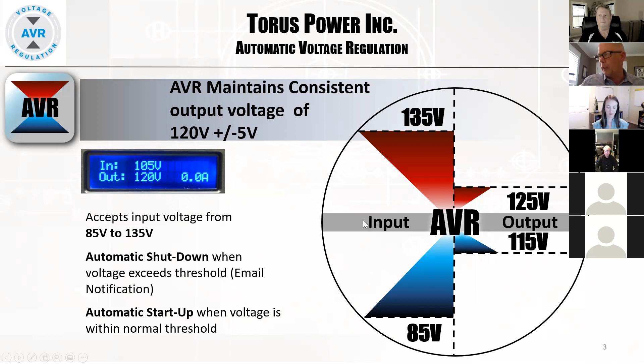So what we do on the automatic voltage regulation units is we have different starting points or different input taps on the primary winding. So we can change the size of the primary winding in relation to the secondary winding. We're looking at the voltage that's coming into the environment and changing the input tap with a series of relays to make sure that the output voltage is a consistent and stable 116 to 124 volts, as I mentioned before. And this is our automatic voltage regulation system. So that's the number 2 point for today's topic.